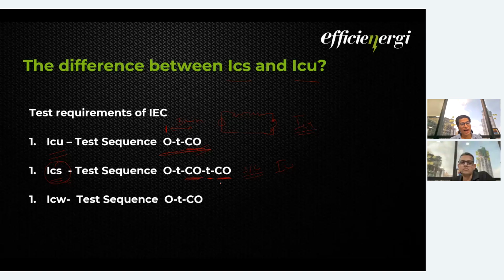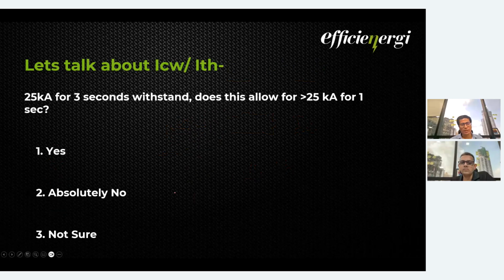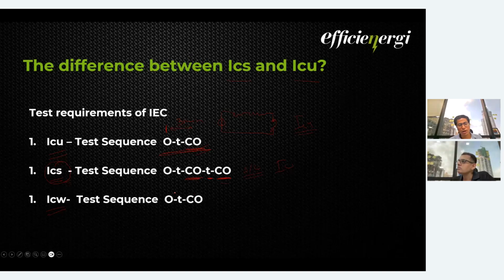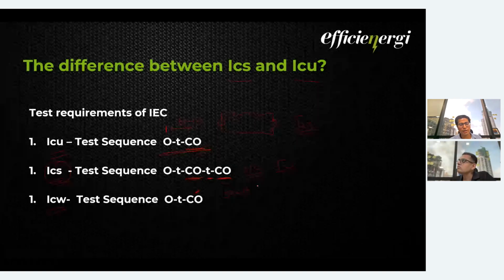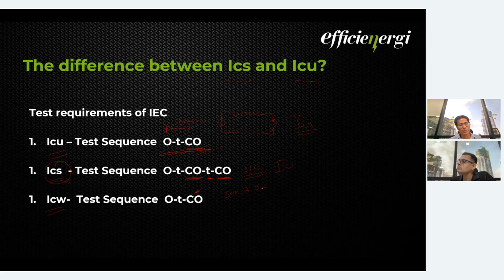Then there is the ICW, the withstand capacity. Open T, and between the close and open operation, there will be some time gap. So if the breaker manufacturer says 50 kiloampere for 5.5 seconds, then for this value there will be a hold, no tripping of the breaker occurs, and then there is an opening of the breaker. After this test, the breaker is checked again, and if there is no damage on the breaker, then ICW is passed. So that is basically the difference between the ICS and ICU.